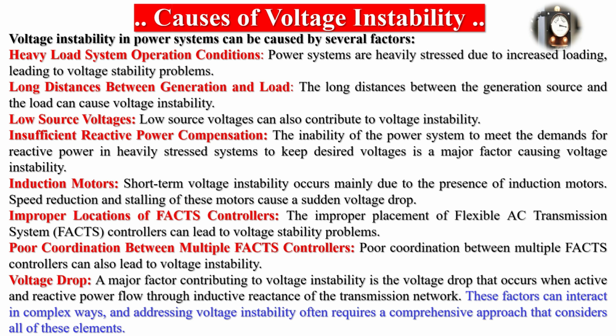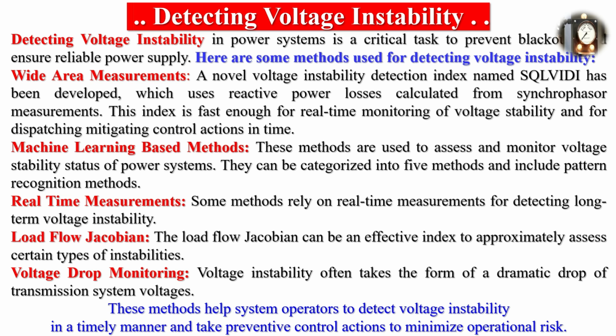These factors can interact in complex ways, and addressing voltage instability often requires a comprehensive approach that considers all of these elements. Detecting voltage instability in power systems is a critical task to prevent blackouts and ensure reliable power supply. Here are some methods used for detecting voltage instability. Wide area measurements. A novel voltage instability detection index has been developed, which uses reactive power losses calculated from synchrophasor measurements. This index is fast enough for real-time monitoring of voltage stability and for dispatching mitigating control actions in time. Machine learning-based methods.